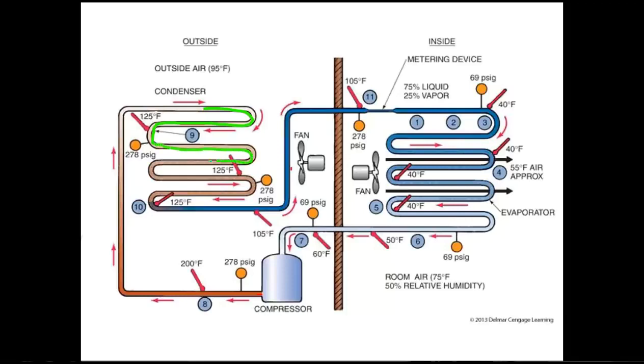As it travels through the condensing coil, all of that tremendous amount of heat energy is being released. And again, if we have a thermometer at any point in the condensing coil, as long as we're at the saturation point, it's 125 degrees Fahrenheit.